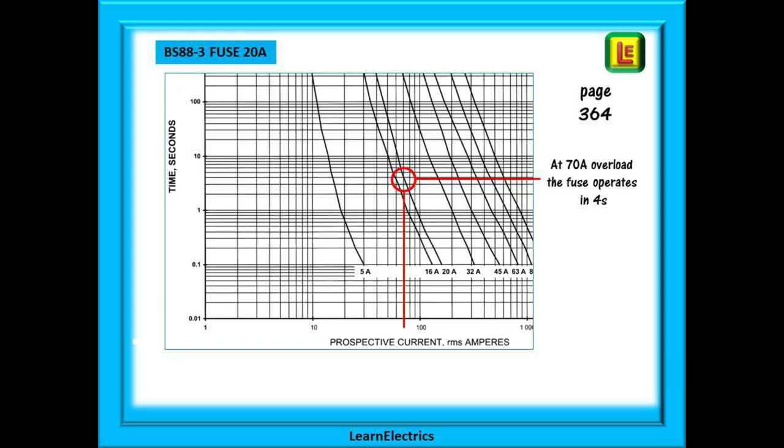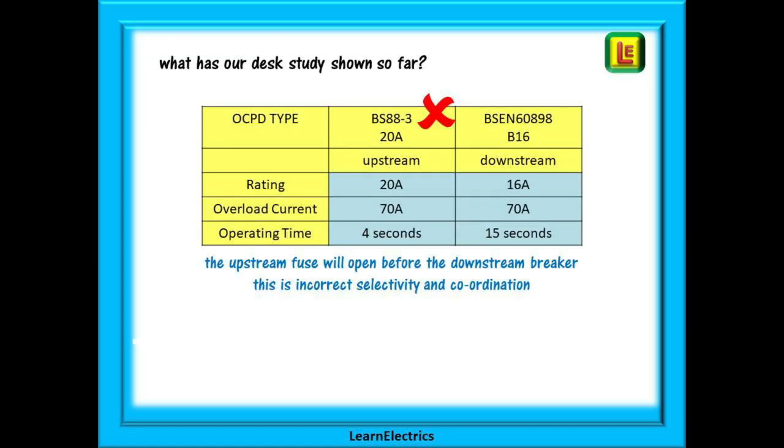First find the chart on page 364. Now look for 70 amps along the bottom and follow this up the vertical line until it meets the curve for a 20 amp fuse. Then check the seconds on the left hand side and we have a response time of 4 seconds. So a 20 amp BS88-3 fuse with the same 70 amps of overload current will operate in 4 seconds. If we put these into a table for comparison we can see that the upstream device the fuse will operate long before the downstream MCB. This is clearly incorrect selectivity and bad coordination.